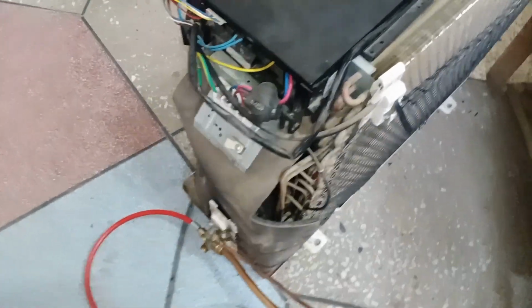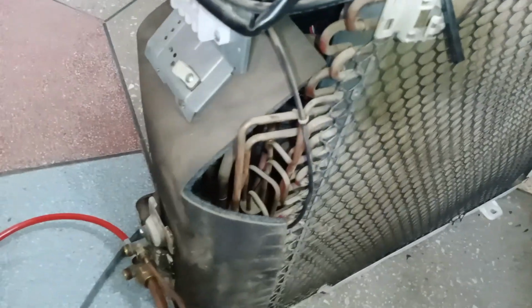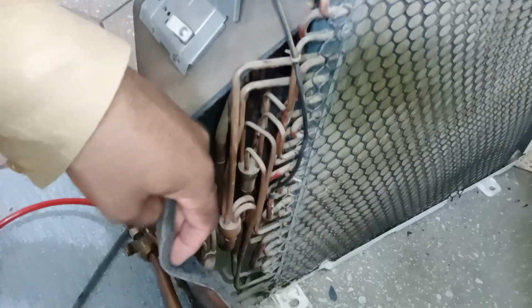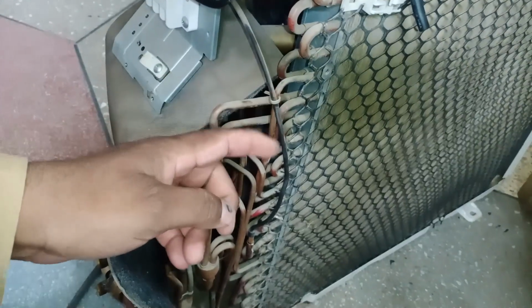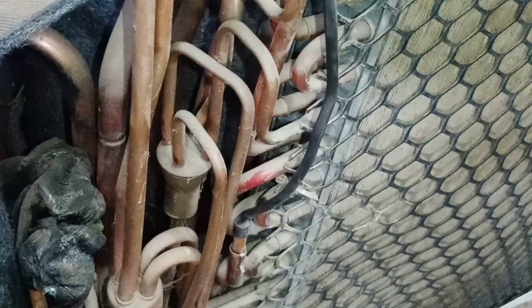Now, let me show you where the condenser pipe sensor is installed in the outdoor unit. I have removed the cover, and you can see the wires coming from the top. This is where the sensor is installed. I will zoom in so you can see clearly. This is the condenser pipe sensor. If this sensor becomes faulty, the system will display error 1.